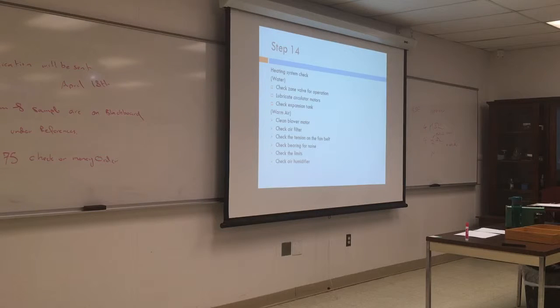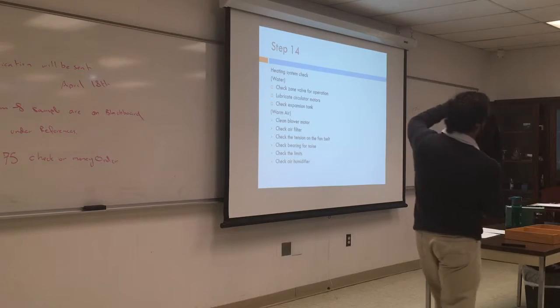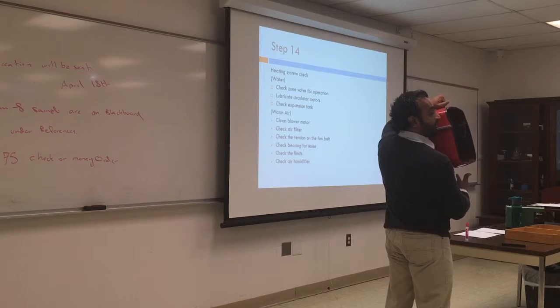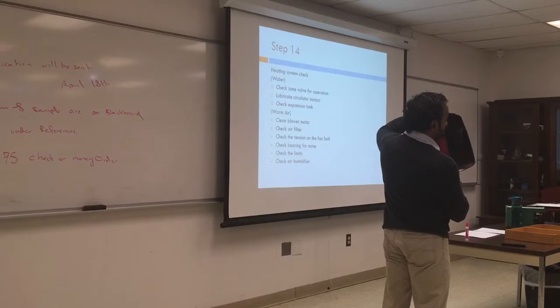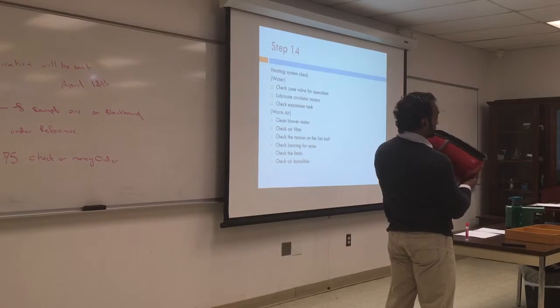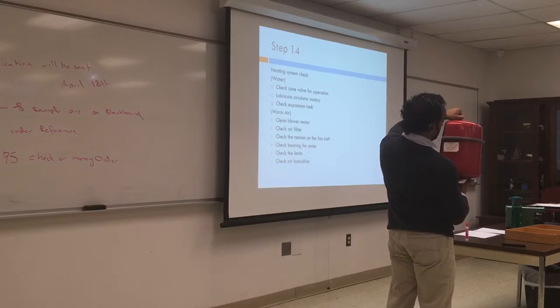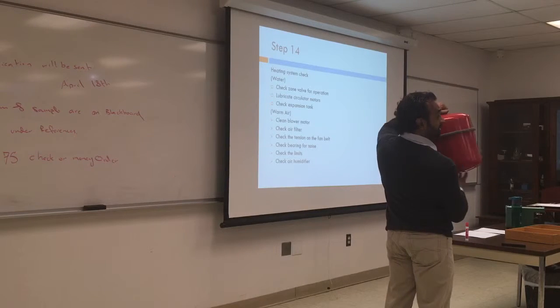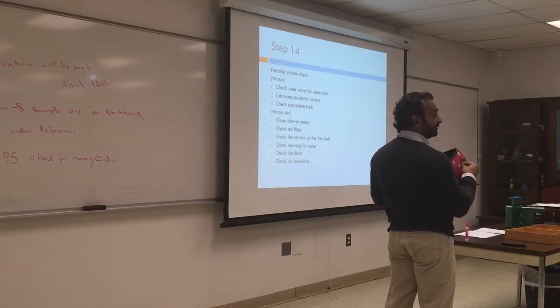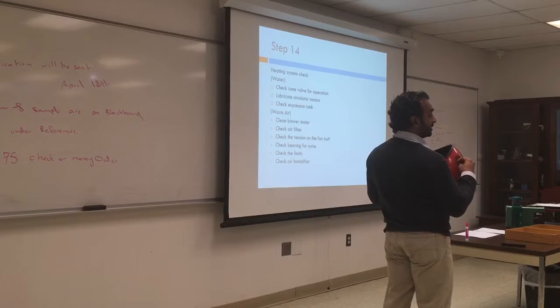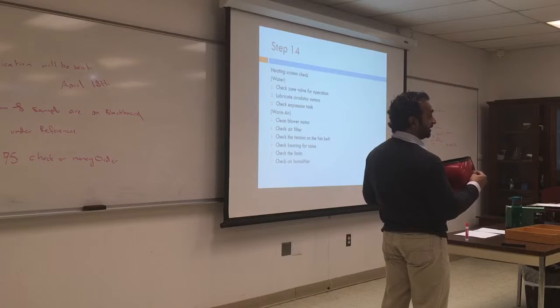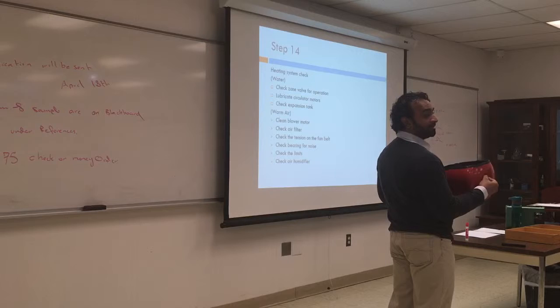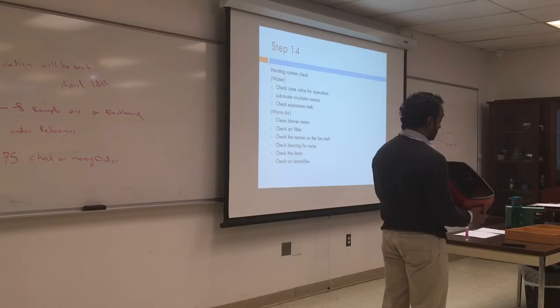So this is the expansion tank. Usually it's hanging from the pipe around the boiler, and this part here is pressurized. So make sure it's the right pressure, and if you look in here, it will tell you it's 12 psi. So you'll open the Schrader valve and go with the pressure gauge and make sure it's 12 psi. If not, you might have to pressurize it. Think of buying a small bicycle pump and pumping air into it. That will pressurize that.